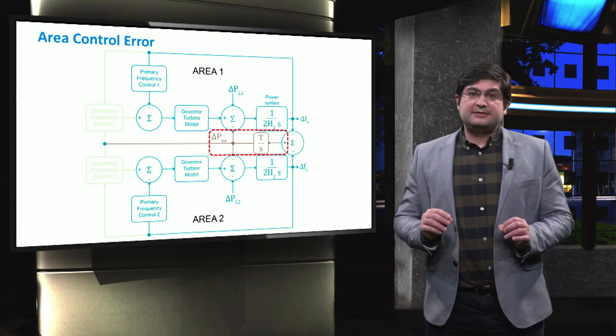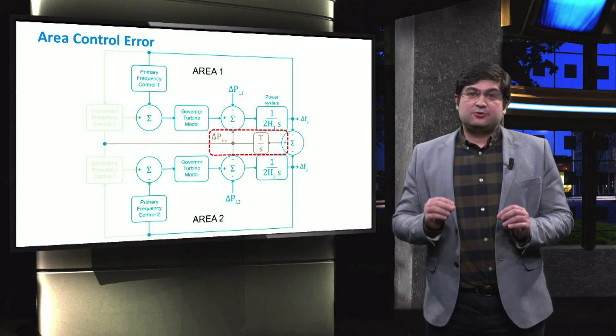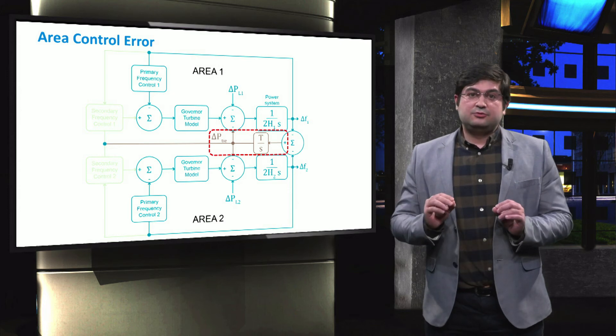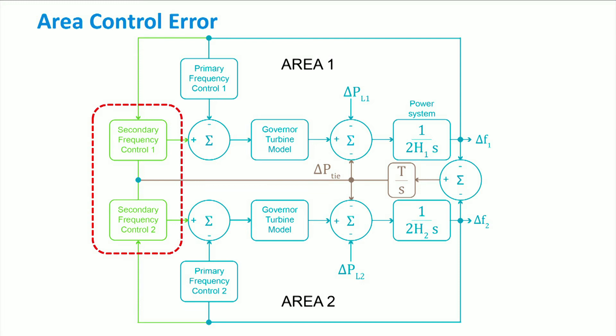We present the frequency control schemes of two areas which are connected to each other through a transmission line. Within each area, we refer to the area control error, or ACE, as the excess or the deficiency of a certain amount of active power. This error is not only eliminated by the generating units within the area, but also partly covered by the other areas through the tie line. The amount of the power which is being exchanged between two areas during the disturbance is obtained according to the frequency deviations in these two areas. Finally, the frequency of each area is adjusted to the nominal value through the secondary controllers.